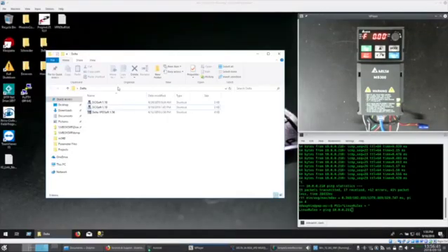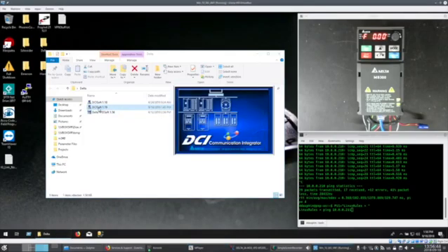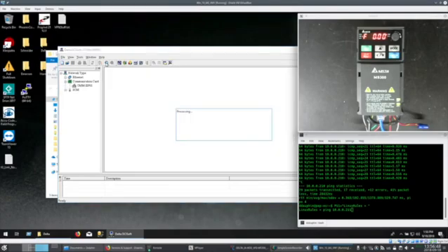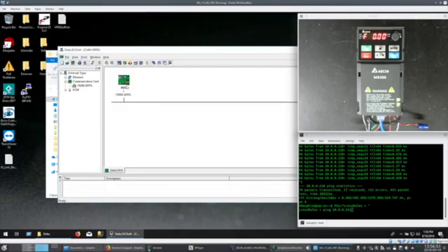To set the IP address I'm going to use DCIsoft. I'm running version 1.19. Just hit this little M button at the top. Seems to search the network. There's my card on my drive, a CMM-EIP01. I double click on it. It should quickly come up.